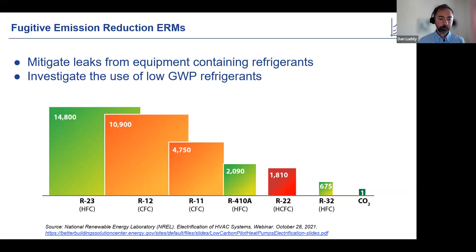There's also an opportunity to investigate the use of low GWP refrigerants for future equipment. Some refrigerants with high GWPs are actually being phased out. R22 has already been phased out, and R410A is currently being phased out. So if you have older equipment, it may be more difficult to service in the future, and that may impact your decisions of when to replace certain chillers, air conditioning systems, or refrigeration systems, and what you would shift to.